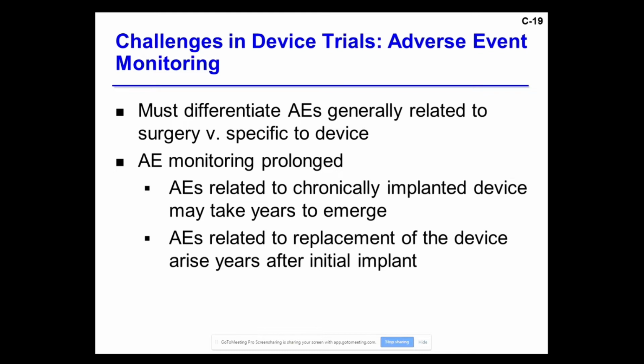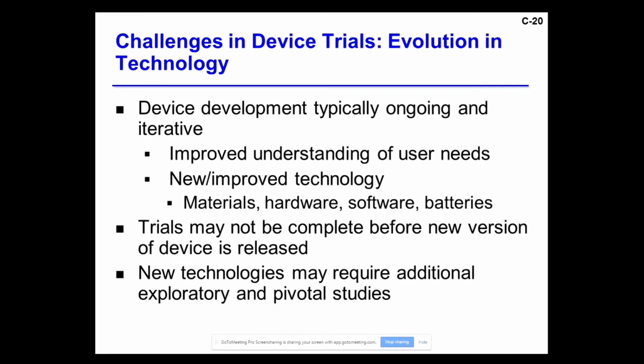And then all of these have batteries, and the batteries run out, and the device has to be replaced. And so you have to track adverse events that may be related to the replacement of the device or related to explantation of the device, such as adverse events from trying to remove a lead that may be adhered to the vagus nerve or may have gliosis in the area of brain in which the lead is implanted. So what are we really saying here?